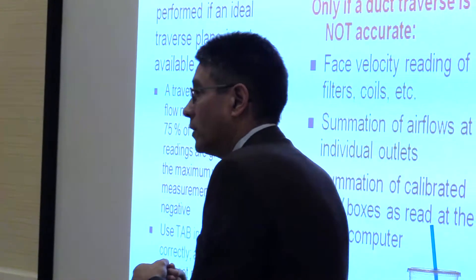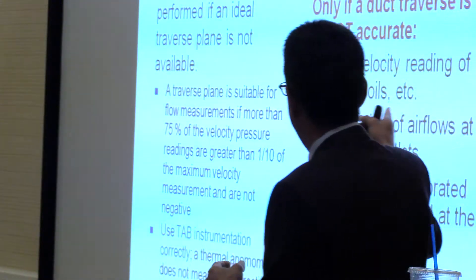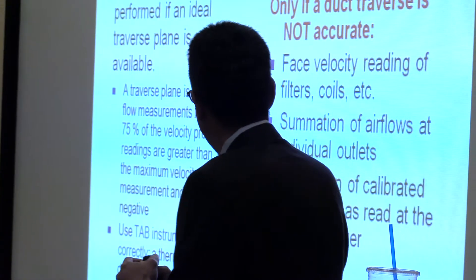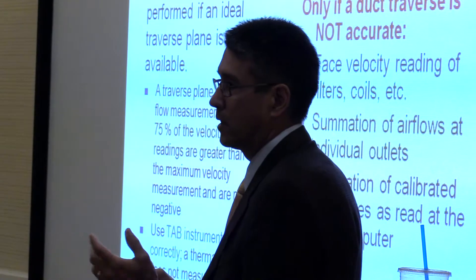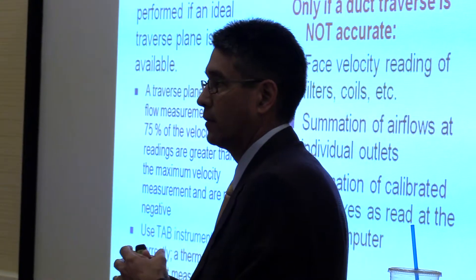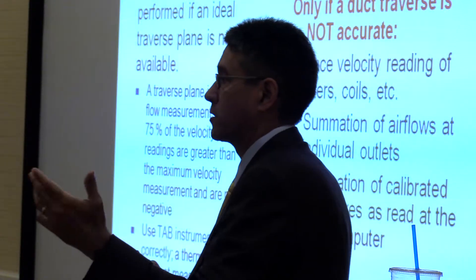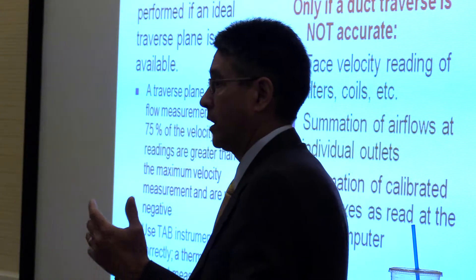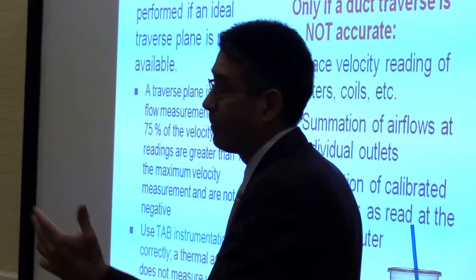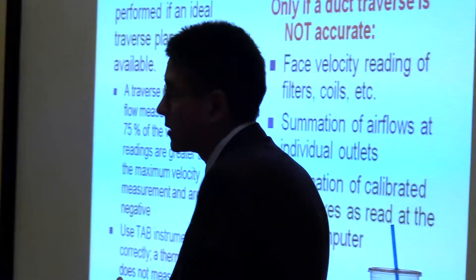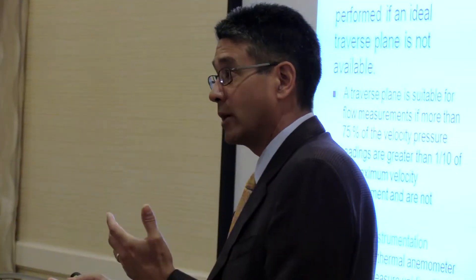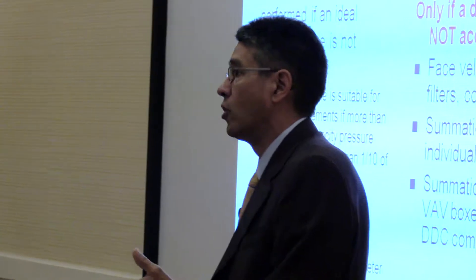Only if a duct traverse is not accurate do we start getting creative — a face coil velocity, a filter velocity reading, or possibly airflow from the outlets. That can get interesting if you have duct leakage or lots of outlets. Another option is summation of calibrated VAV boxes: once all the VAV boxes are calibrated, open the system up and read those airflows off the computer. You're at the mercy of DDC system tolerances and measurement tolerances, but it's better than nothing.